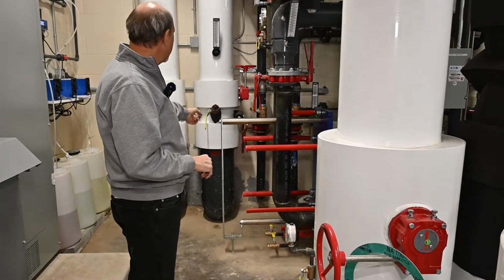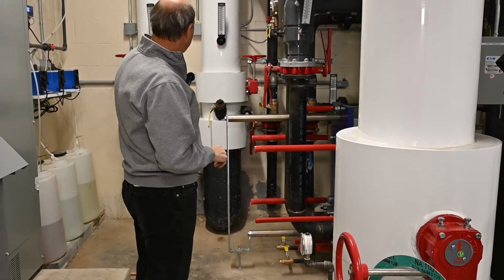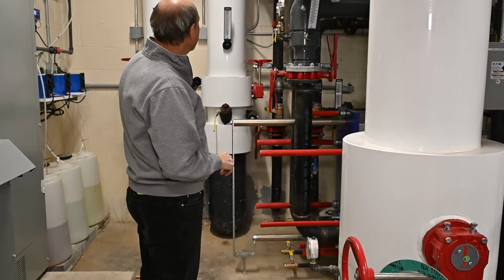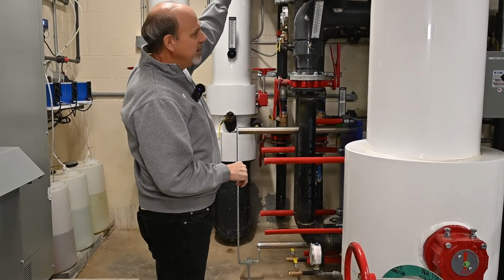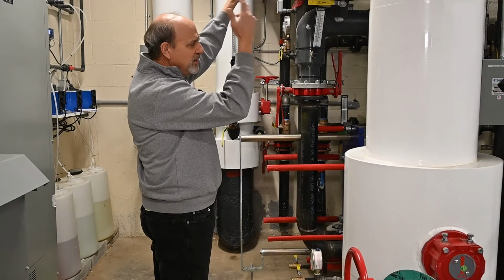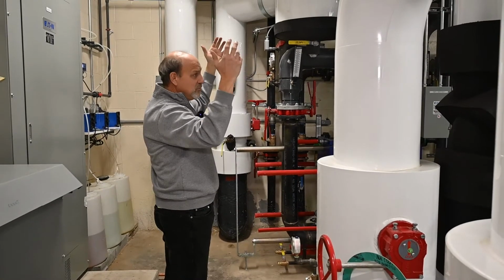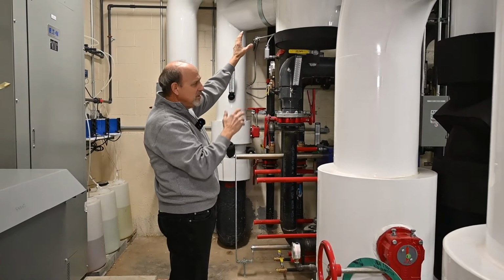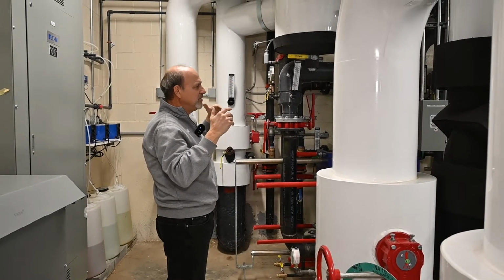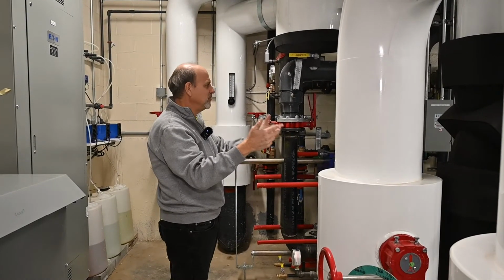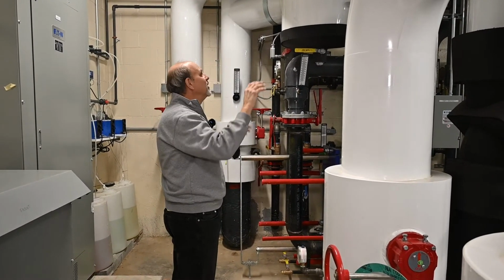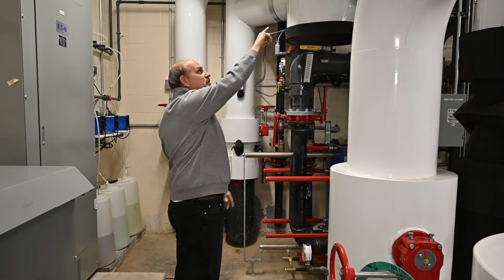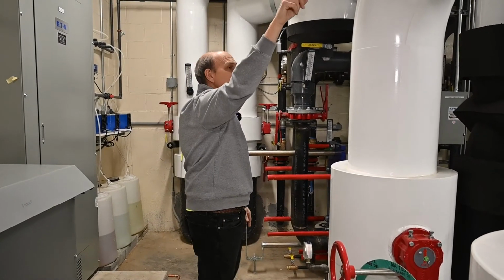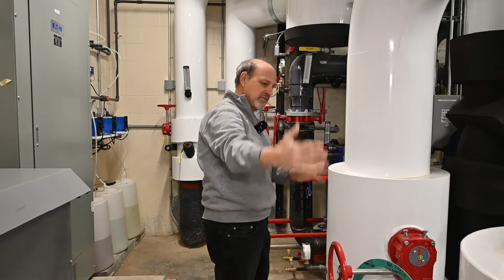Main return comes in here. You got temperature thermometers on each of the supply and return. Comes through here, goes through an air separator designed to purge out the air. Once you get the air out of the system, which we have, this isn't used that much more unless there's been air introduced to the system, which we don't want to have that happen. But anyway, it's an air separator that's in the system. Basically, that 8-inch line comes down here, goes to the suction of both of these pumps.